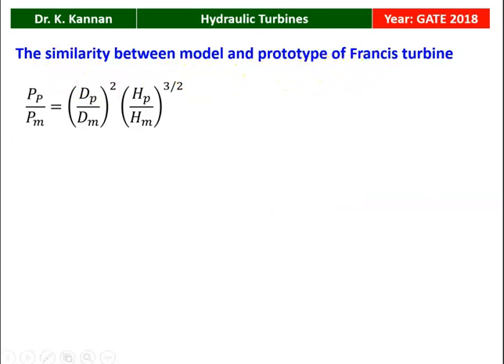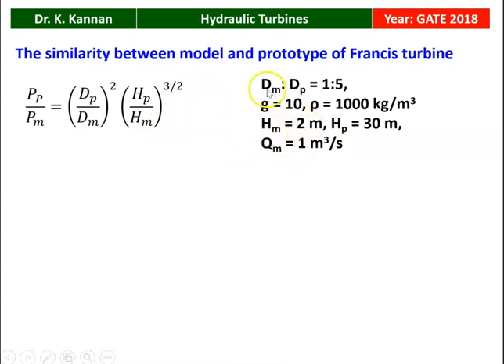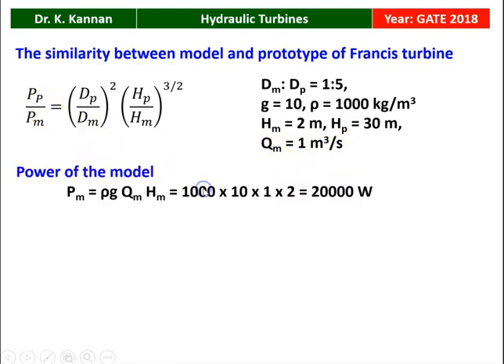The similarity between model and prototype of a Francis turbine: power of the prototype divided by power of the model equals the diameter ratio (diameter of prototype divided by diameter of model) to the power 2, multiplied by the head ratio (head of prototype divided by head of model) to the power 3/2. Given: scale ratio diameter of model to diameter of prototype is 1/5, G = 10 m/s², density = 1000 kg/m³, head of model = 2 m, head of prototype = 30 m, discharge of model = 1 m³/s. Power of model = ρGQ_M × H_M = 1000 × 10 × 1 × 2 = 20,000 watts.